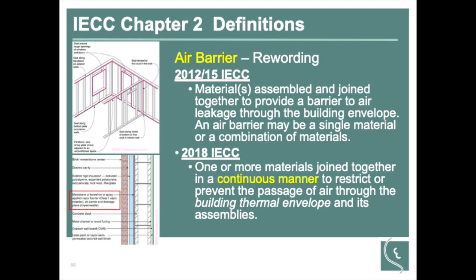Air barrier, again, the code is really noting, identified that the biggest thing with air barriers is making sure of continuity, that they are continuous air barriers. And so, trying to clean up some of this wording, in 2018 they added "continuous manner" to really hit home the point that this air barrier has got to be continuous. You put a little hole in, and it's amazing how much air can fit through a 1-inch hole or even just a little 1/8-inch gap around the electrical box.